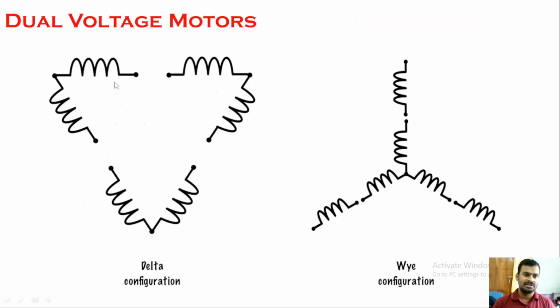The wiring configuration inside the motor will look like this. Each phase coil will be split into two different coils. These coils can be connected either in series or in parallel according to the requirement, whether you are going to use it in a high voltage configuration or in a low voltage configuration. Also, the motor manufacturer itself will specify whether the motor is a star connected motor or a delta connected motor. Based on that, they make the configuration inside so that these two coils are connected in such a way that it forms either a star connection or a delta connection.